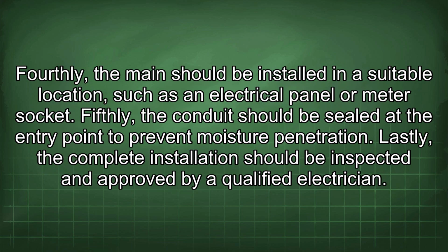Fourthly, the main should be installed in a suitable location, such as an electrical panel or meter socket. Fifthly, the conduit should be sealed at the entry point to prevent moisture penetration. Lastly, the complete installation should be inspected and approved by a qualified electrician.